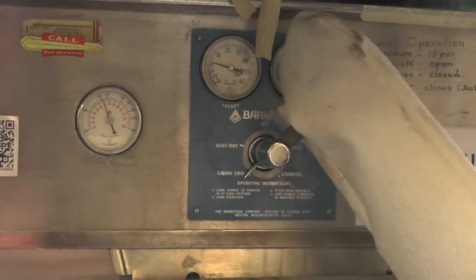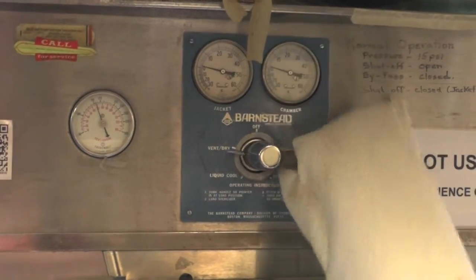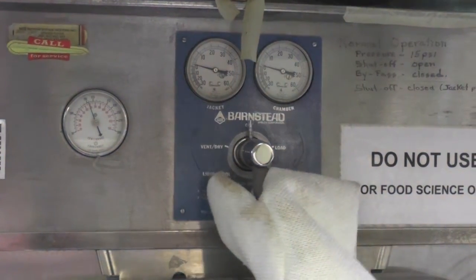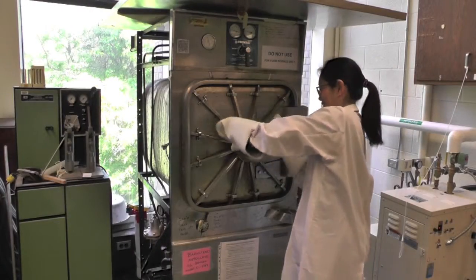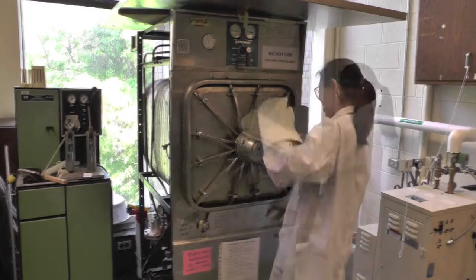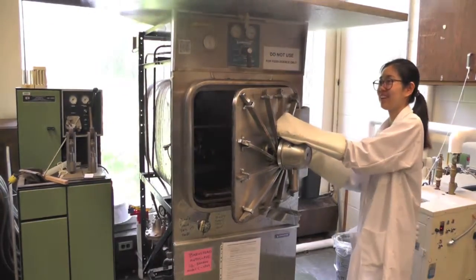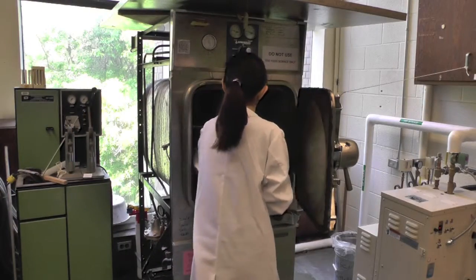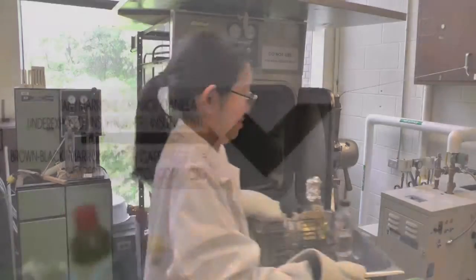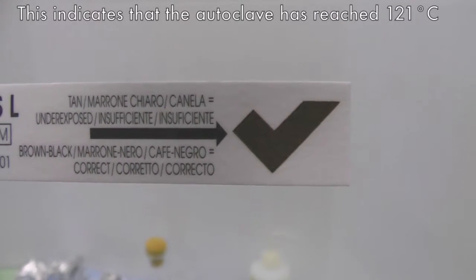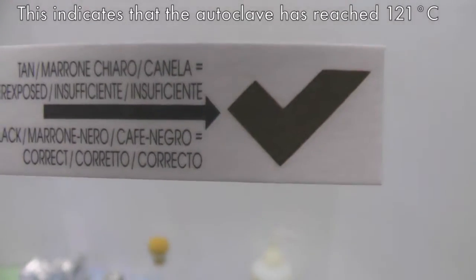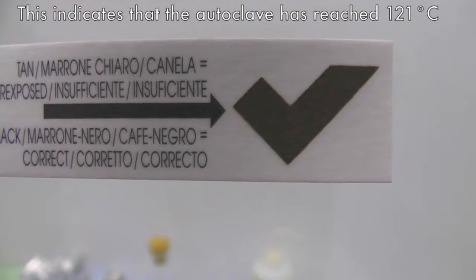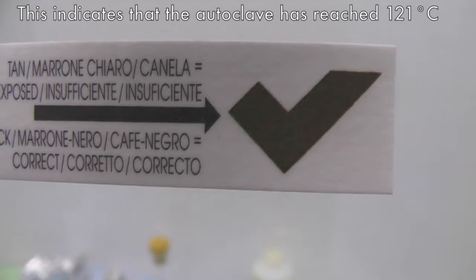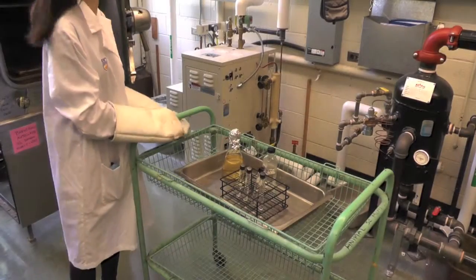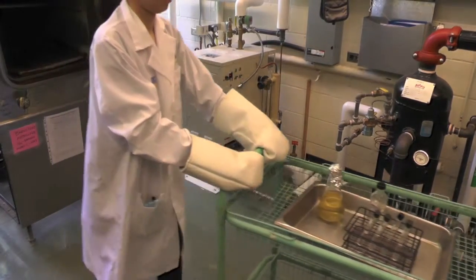When the chamber pressure has returned to 0 psi, turn the knob to off position. Carefully open the autoclave door and avoid facing the opening in case of steam burn. With oven mitts, take out your materials. The check mark on the chemical indicator strip should turn black to indicate that the internal temperature of the autoclave has reached 121 degrees Celsius. Leave the autoclave door open to cool.